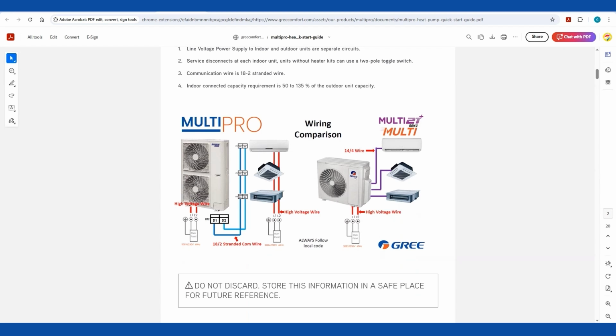You're going to put power to the outdoor unit, and then you're going to run a 14-4 wire to each individual head, and that powers those indoor heads. MultiPRO is different. You are going to put power to the outdoor unit. You are going to have a separate power source to your indoor units. And then you're going to use an 18-2 stranded comm wire that is going to go from D1 to D2 and daisy chain through. Significant difference.